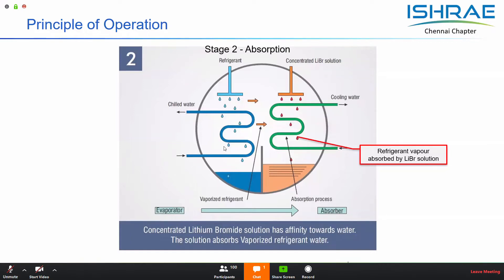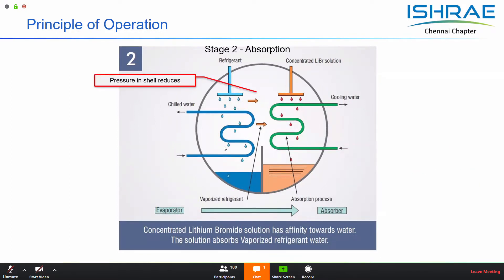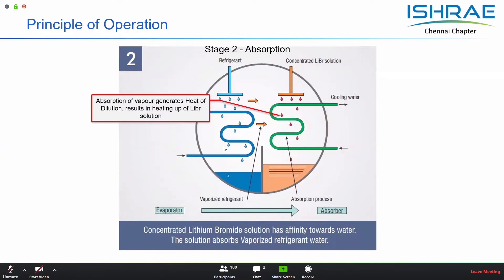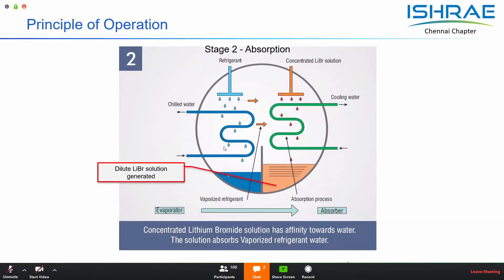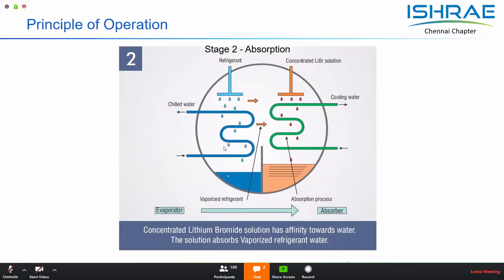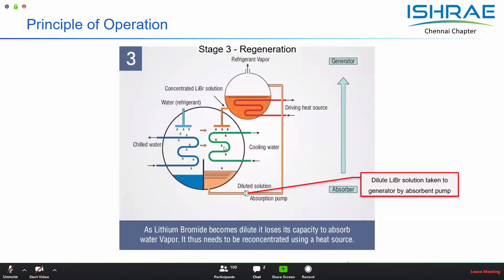If the temperature of the lithium bromide increases, its affinity reduces. To overcome this, cooling water is circulated through the absorber to take away this heat of dilution. This is one major area where it differs from electrical systems — there is heat rejection in two heat exchangers: one is the condenser and the other is the absorber. The cooling water takes away the heat of dilution and this absorption process continues until the refrigerant vapor is absorbed and a lean solution is generated. This lean solution is unable to absorb any more because it has become saturated.